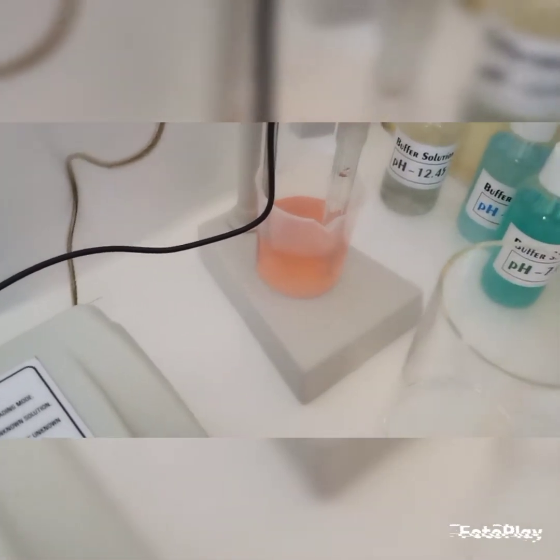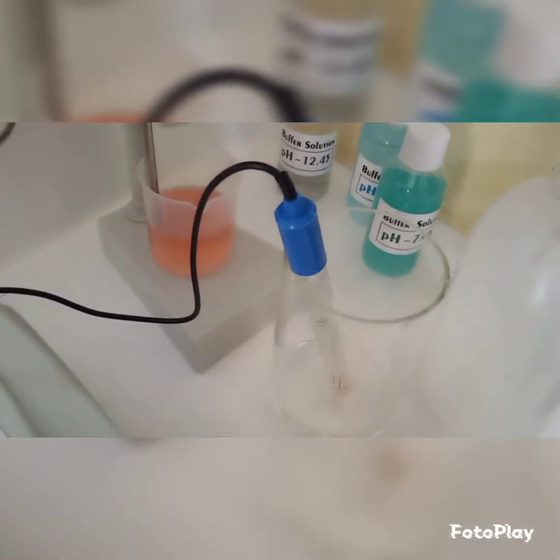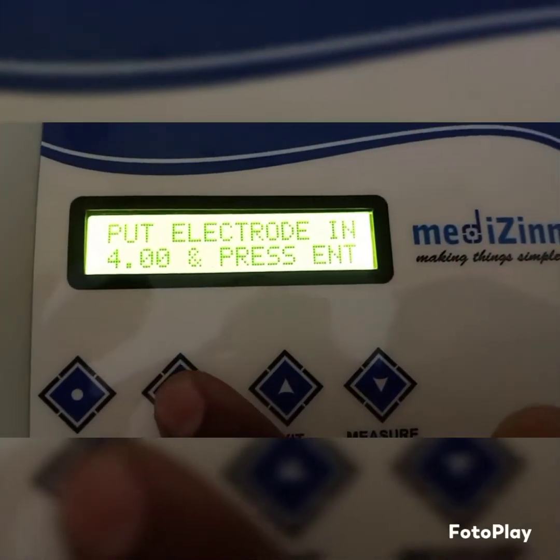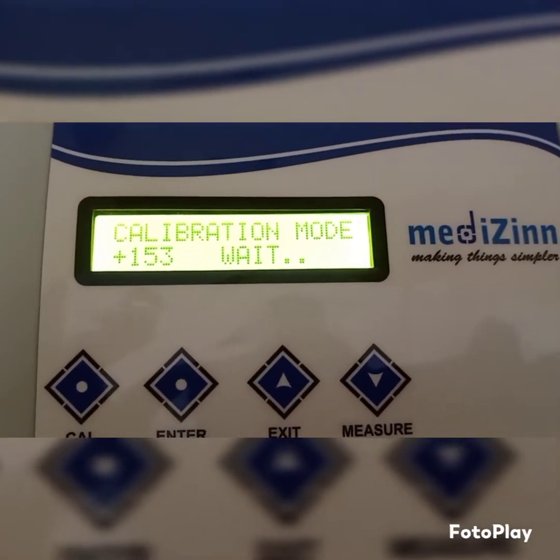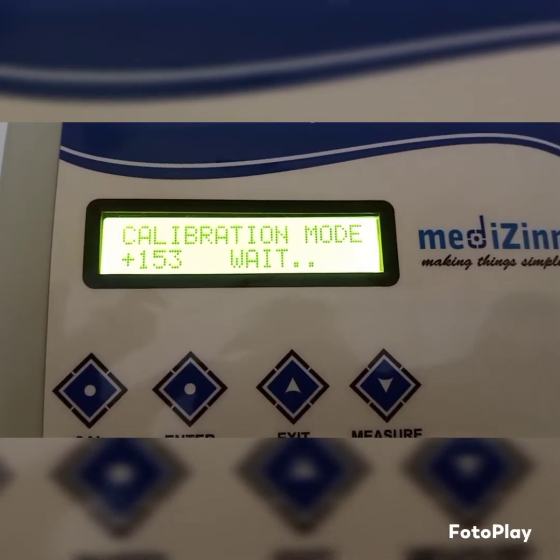Now move the solution into the 1.68 bottle from the beaker and wash the electrode thoroughly with the distilled water before putting the electrode into 4 pH. Also wash the temperature probe with the distilled water. Put both electrode and temperature probe into 4 pH solution and after that press enter. Now again analog value, it's around 153.